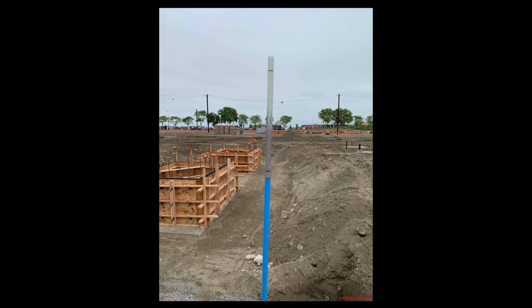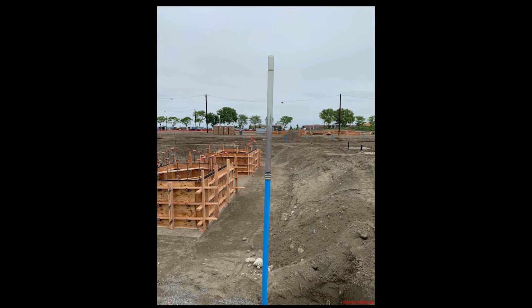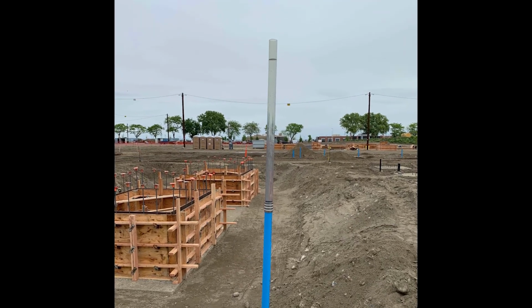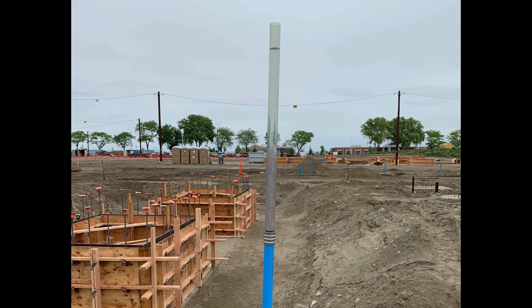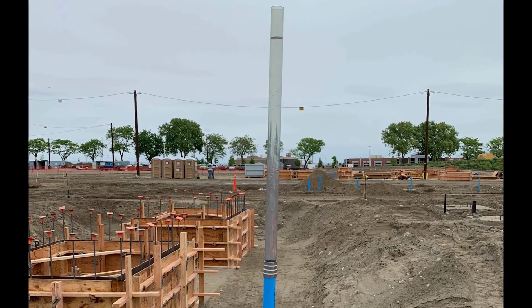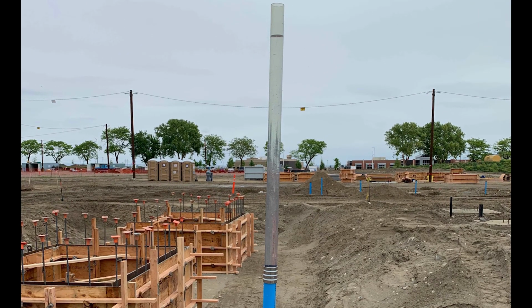One special attribute for an inspection and test we performed on underground plumbing, including process, sanitary, and sewer, was that we utilized a piece of clear PVC on top of the pipe to alleviate any ladders being used for ladder safety. This created a window to actually see the water level and made it easier for our inspectors to verify that the head test was performing.